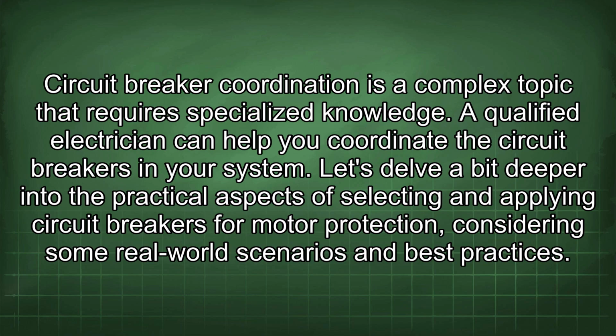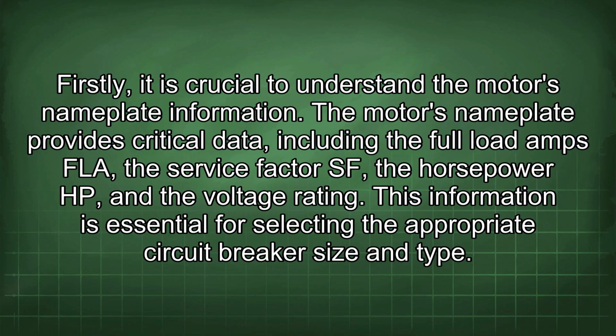Let's delve a bit deeper into the practical aspects of selecting and applying circuit breakers for motor protection, considering some real-world scenarios and best practices. Firstly, it is crucial to understand the motor's nameplate information. The motor's nameplate provides critical data, including the full load amps (FLA), the service factor (SF), the horsepower (HP), and the voltage rating. This information is essential for selecting the appropriate circuit breaker size and type.